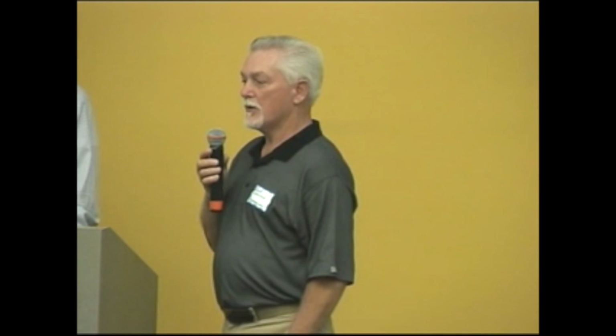Now, let me explain the operation of the system. The way it operates is there is a lockout that locks it out if the ambient air temperature is below a certain degree, which is normally 60 degrees. If it's above 60 degrees and your system is running, which means your compressors are running, your condenser fans are running, then we are allowed to operate. 60-degree dry bulb, but we use total enthalpy to determine whether we operate or not. We have a humidity sensor as well as an ambient temperature sensor to determine that. We operate based on head pressure or liquid line temperature. So we have a sensor that sits on the liquid line, and we determine based on the refrigerant type what the optimum head pressure should be.